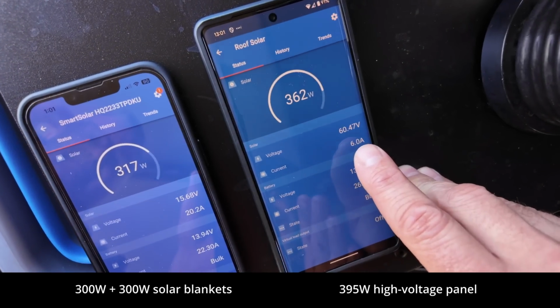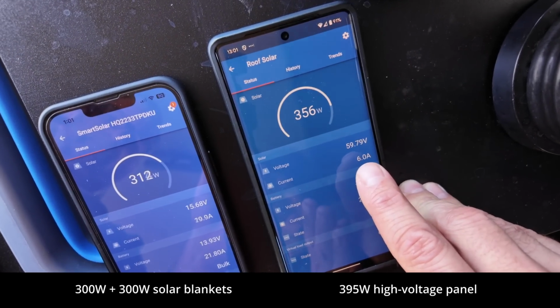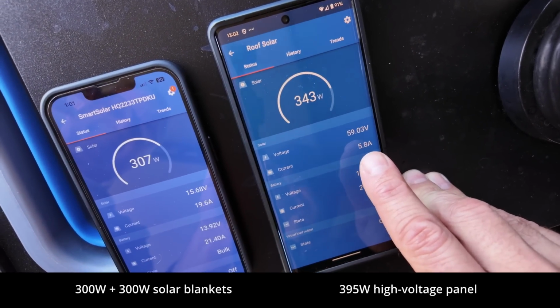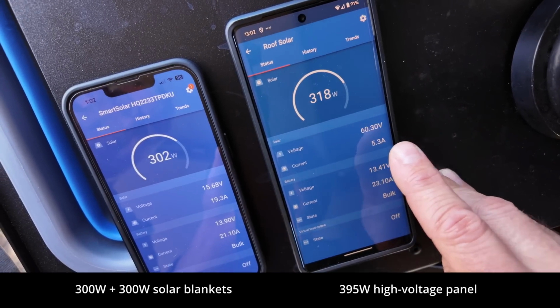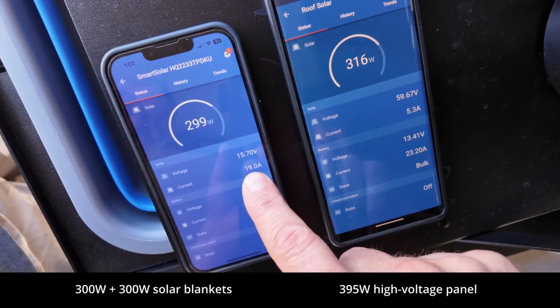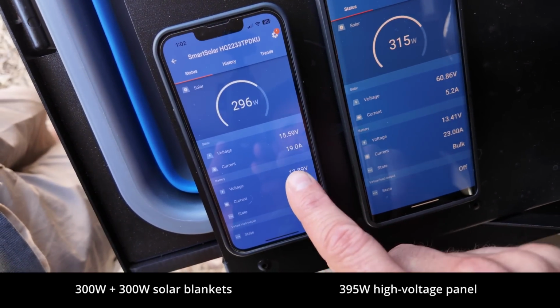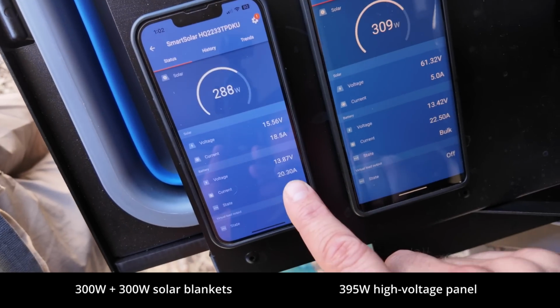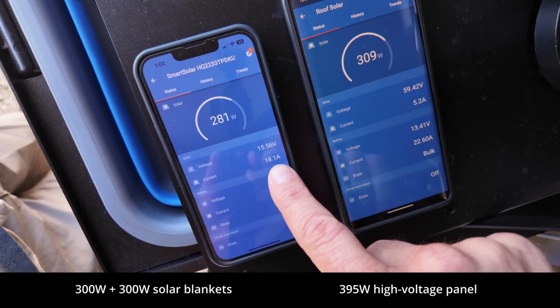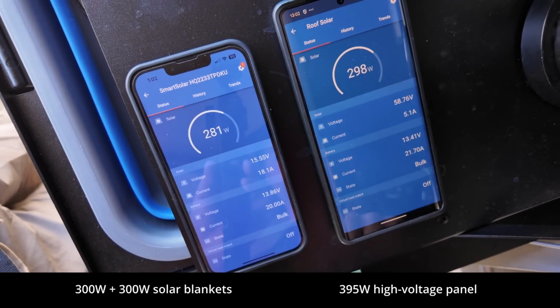That's a big difference between a high voltage panel, where the voltage has dropped a bit too, from 64 volt MPPT to roughly just under 60, but that's not a big problem. Here though, if it drops too far, we're getting too close to the battery voltage, and the MPPT struggles to get enough power out of those panels.